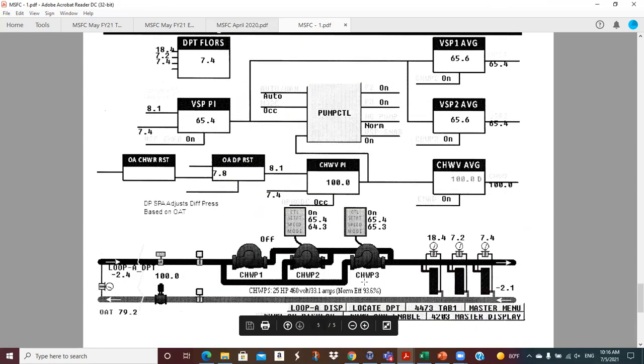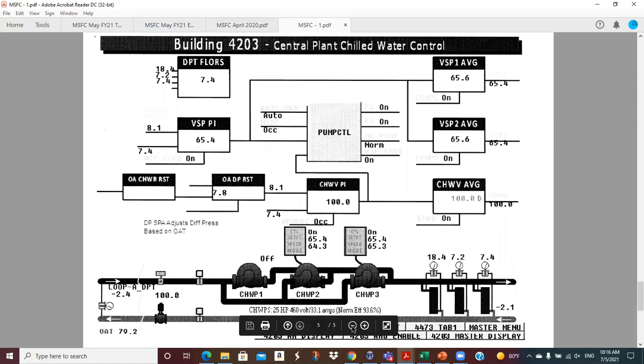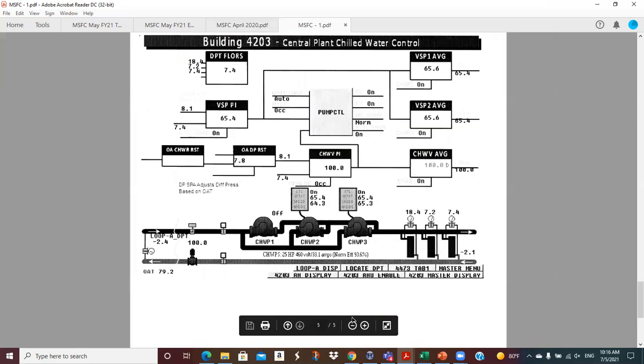Okay, and then we did go to the central chiller plant, which looked to be extremely well run. We mentioned the central chill water plant, so they printed this screen out and gave it to us. They've got VFDs on just about everything. They had a big 5-cell cooling tower, had VFDs on all of those fans, and they seemed to be reasonably controlled. We probably spent 30 minutes walking around the chill water plant.